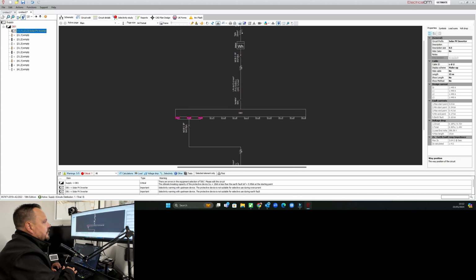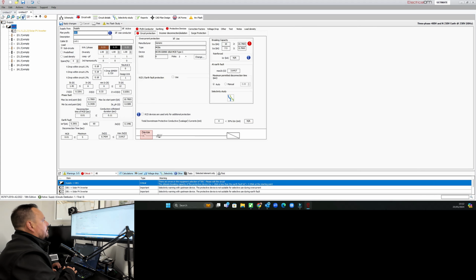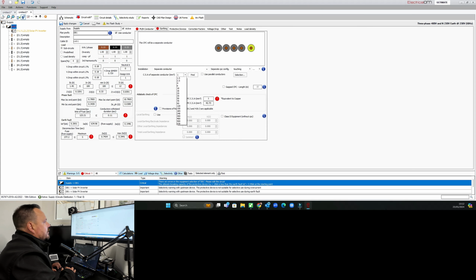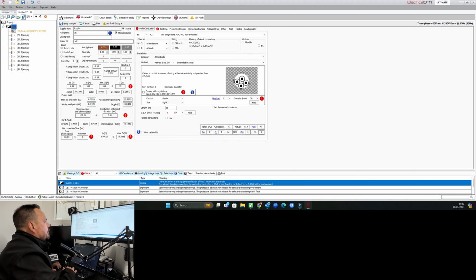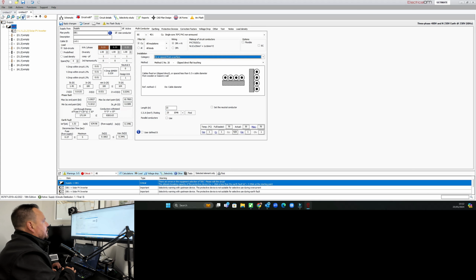So first up is to change all that. So with the supply circuit from the meter, if we go back into that, we're not going to use any overcurrent protection because that's just off the service fuse. The earthing is going to be a separate conductor, and again we'll have that as 16 millimeters. So we can pop that in there as well. The phase and neutral conductors, again, they're just going to be the tails. So we want those at 25 mil, and they're going to be on our space from a surface clipped direct.